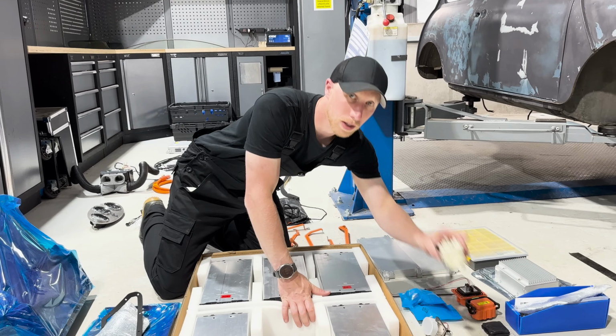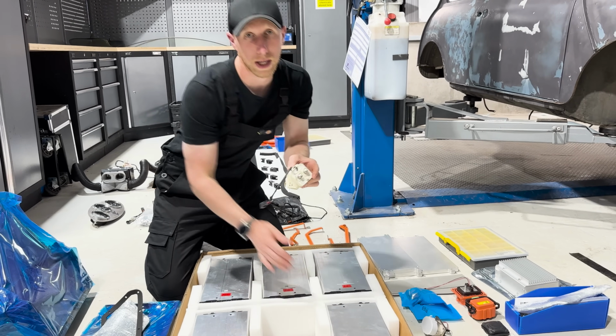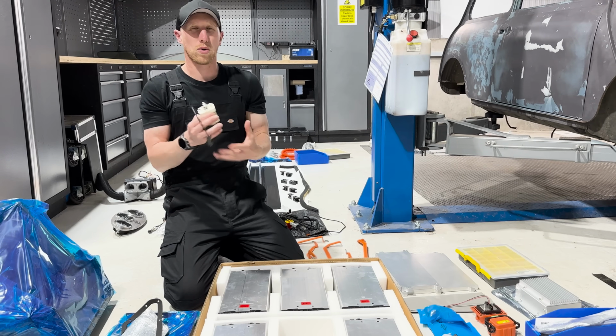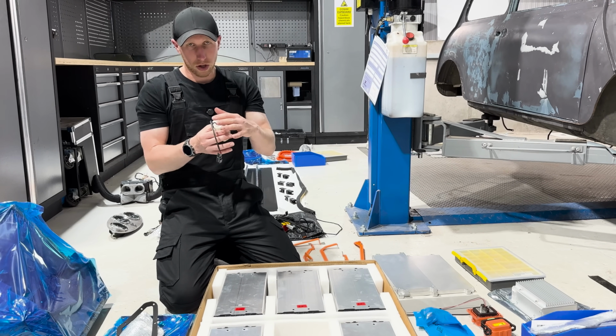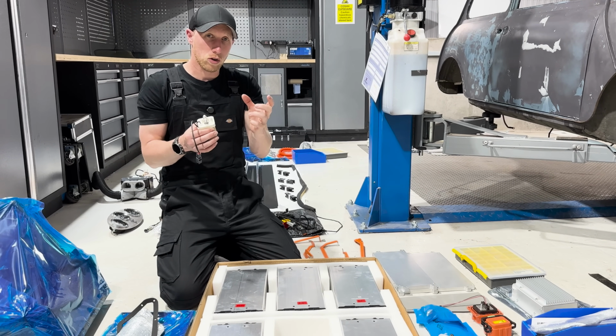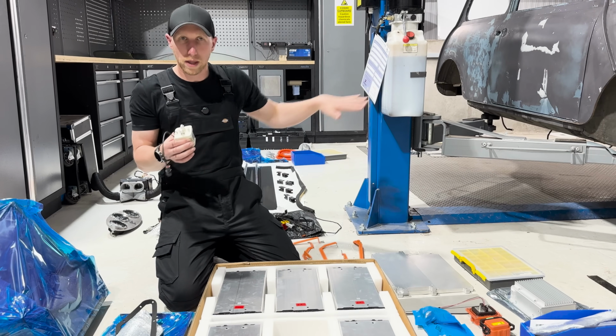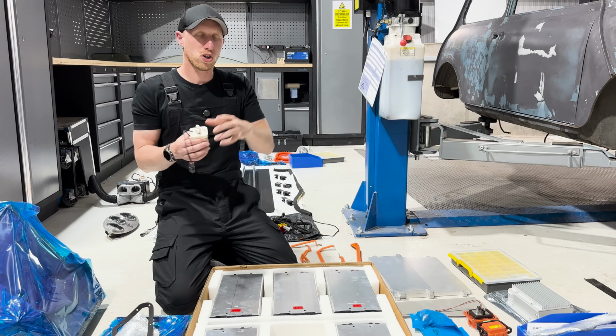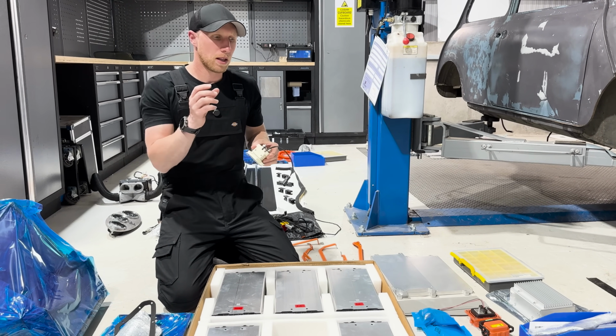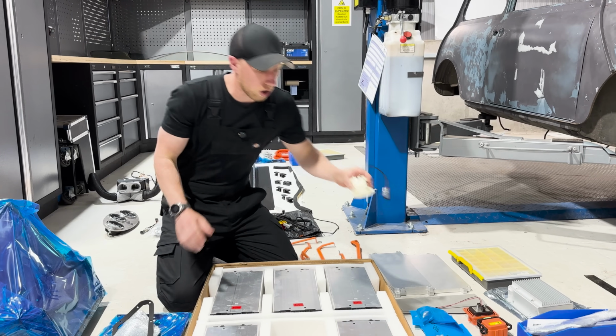You also have contactors in the pack for safety, which open and close, and can also do something called a pre-charge. This shuts a smaller contactor with a pre-charge resistor to bring all the caps and electrical components up to a set voltage before shutting the main contactors, meaning the electrical components have a much longer lifespan.